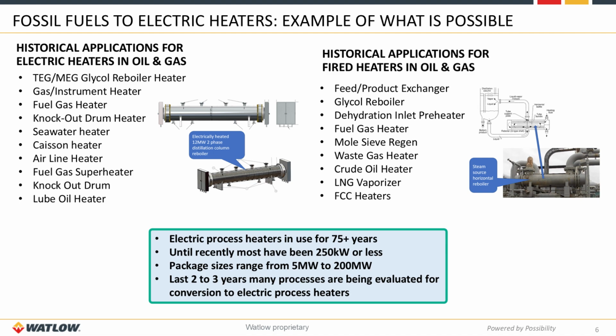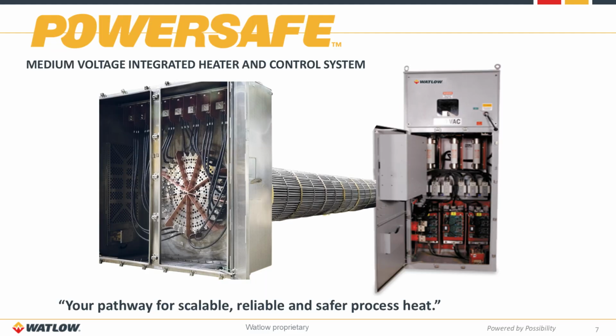For over 75 years, electric process heaters have been used in oil and gas, but mostly at lower power ratings, typically under 250 kilowatts. Now we see heater packages scaling up from 5 megawatts to 200 megawatts, with more industrial processes transitioning to electric heat over the past 3 years. This evolution enables scalable, reliable, and safer process heat for the modern industry. I'll now make the transition to focus more on medium voltage heaters, specifically Watlow's POWERSAFE medium voltage integrated heater and control system. We like to say that this is your pathway for scalable, reliable, and safer process heat.